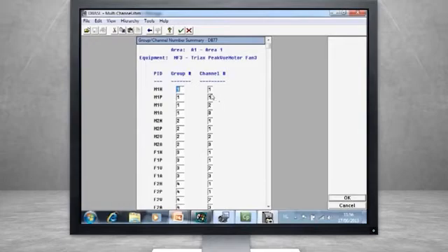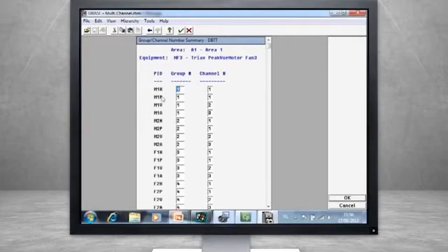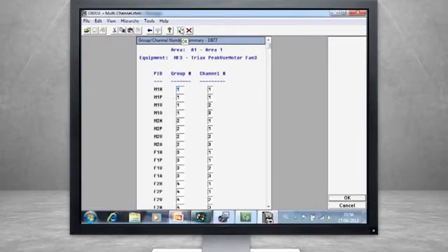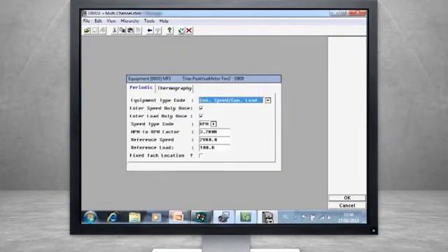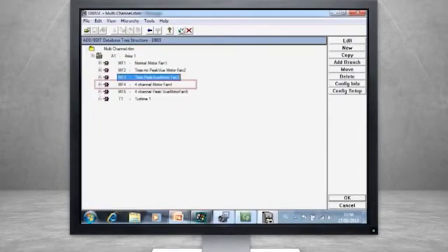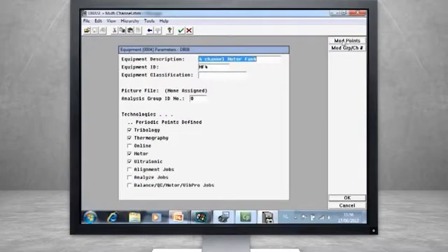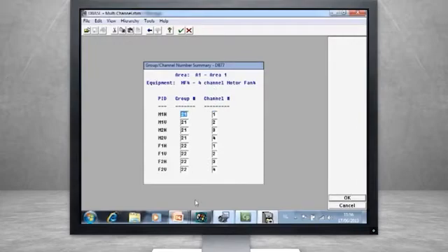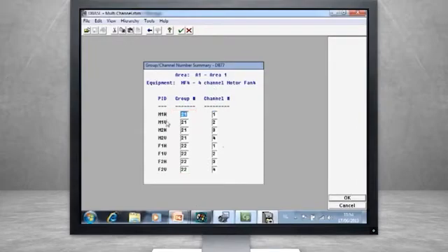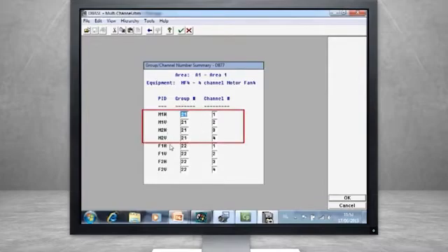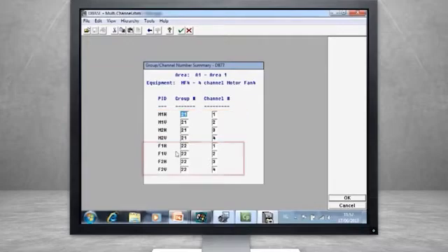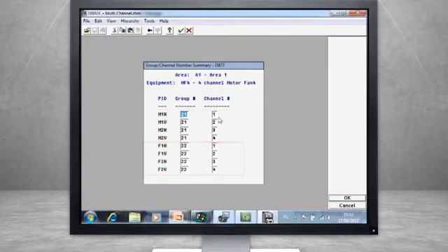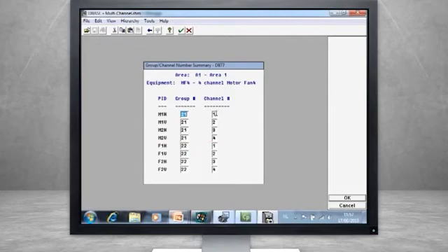The examples we've looked at so far have used triax sensors. If you are working with four separate sensors, you can measure the Motor Outboard Horizontal and Vertical simultaneously with the Motor Inboard Horizontal and Vertical. Let's look at the configuration. Since we are not working with triax sensors now, the group numbers must start with 20 or 21. Since we can measure four channels simultaneously, the Motor Outboard and Inboard Points are in the same group, as are the four points for the fan. The channels are simply numbered 1 through 4.